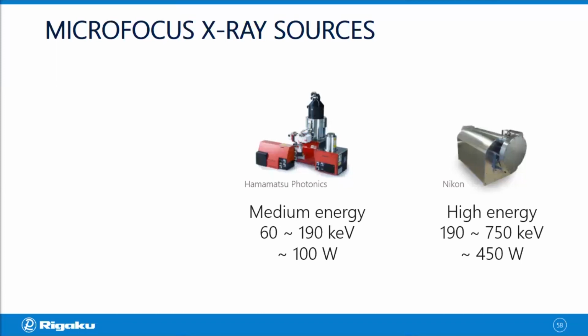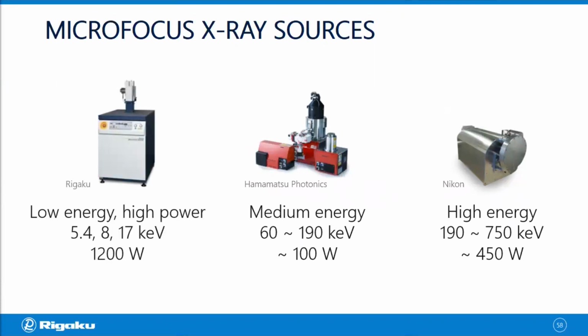If you want to see something light or soft and you want to get high contrast, high resolution image from them, then you're going to have to lower the X-ray energy, but you do not want to lower the power of the X-ray source. In that case, you need a different type of X-ray source like this one. This is a rotating anode type X-ray source, and this particular one is Rigaku 007. And with this generator X-ray source, you can choose the energy from 5.4, 8, or 17 keV, but you are not compromising on the power because you can operate this one at 1200 watts. And this is a good generator to use for light materials to achieve high contrast and high resolution. So those are the three major categories of X-ray sources.